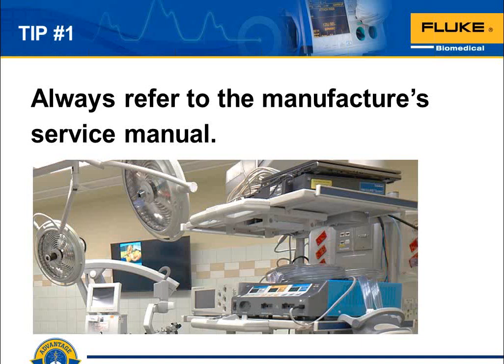Refer to the service manual for performance of inspection tasks specific to the device. These service manuals typically recommend an inspection frequency. Complete the performance inspection per the manufacturer's procedure. And we're going to talk about a way that you can cross-verify the manufacturer's recommended inspection frequency compared with a risk-based assessment that includes a lot of your own information that hopefully you're archiving and databasing in a CMMS, a computerized maintenance management system, or at least in some way an accessible method of getting to what you actually are using as an inspection procedure, because there's several different kinds. So we'll go into that in a minute. So always follow the manufacturer's service manual procedure if you can get it at all.